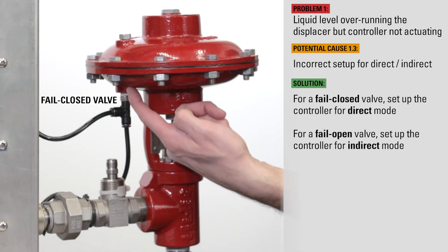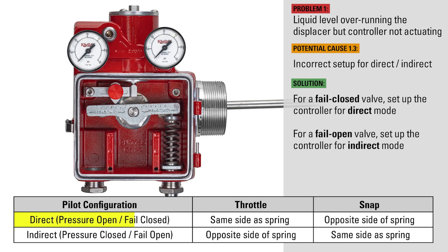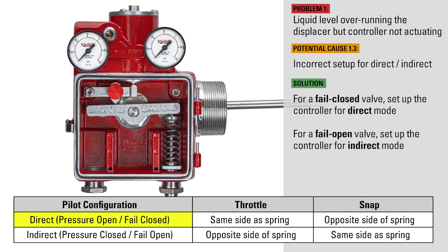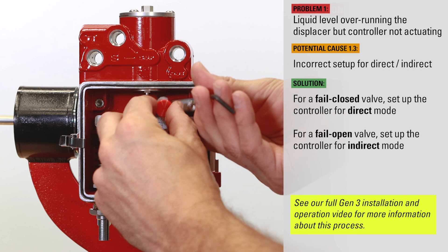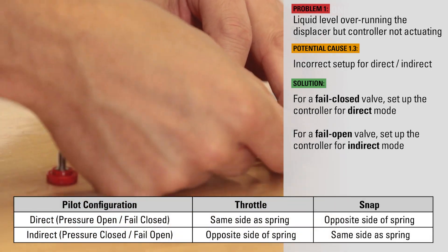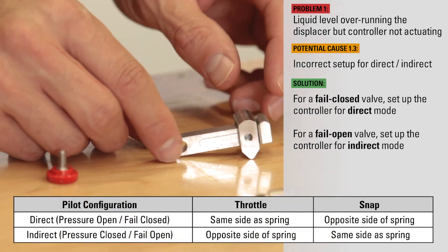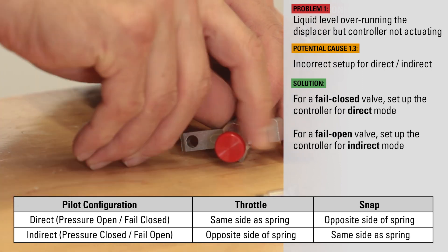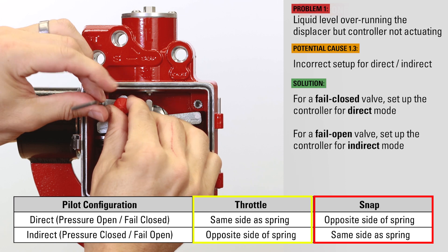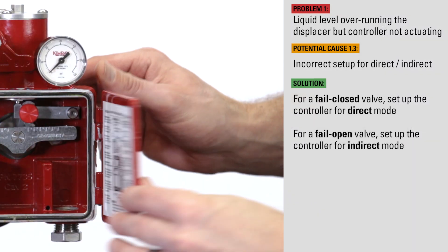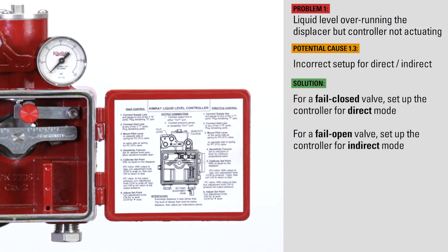For a fail closed valve, the level controller should be set up in direct mode, and for a fail open valve, indirect mode. If set up incorrectly, the controller will not actuate the way you want it to. Just move the pilot lever from one side to the other. This chart found in the installation, operation, and maintenance manual is an easy reference for which side the pilot lever should go on when in snap or in throttle. For your convenience, this information is also given on the inside of the Gen 3 cover.